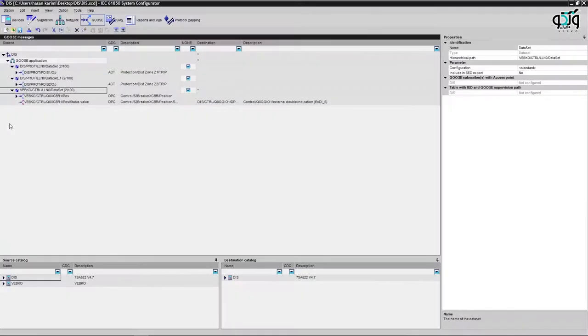Here in IED name, the title DIS stands for distance. By opening the IEC 61850 system configurator, you can select the desired items from the source catalog and destination catalog sections and transfer them to the GOOSE application section to perform GOOSE tests.